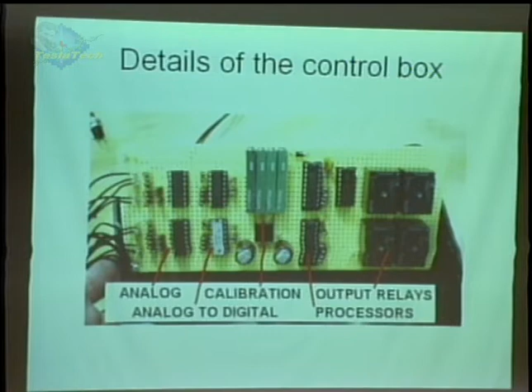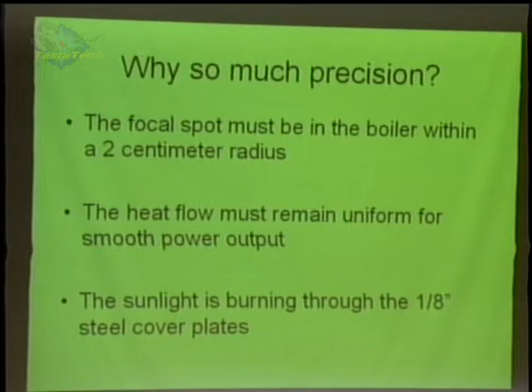Why so much precision? Again, this focal spot has to be within a 2-centimeter radius in the center of that boiler. The heat flow has to remain uniform for that generator to run uniformly. If it gets cold or hot, it's going to change operating speed. And the sunlight's burning through the 1/8-inch steel cover plates. We put cover plates over the insulation because we didn't like seeing melted insulation, and the sun didn't care - it burned right through the 1/8-inch plates.